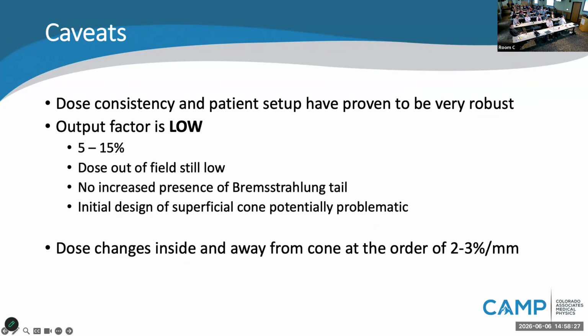So some of the caveats that we found, and this is still very much a garage shop solution. The dose consistency and patient setup were super robust, really easy to accomplish. Just put it on the surface of the patient's skin and you're ready to go. One of the caveats, though, is that the output factor was very, very low. For the smaller cones that we had, it's to the tune of 5%. And so, of course, we're putting a ton of monitor units through this device. But even with that tremendous amount of monitor units, the dose out of the field was still very low. No increased presence of a bremsstrahlung tail, which was an area of concern for us.